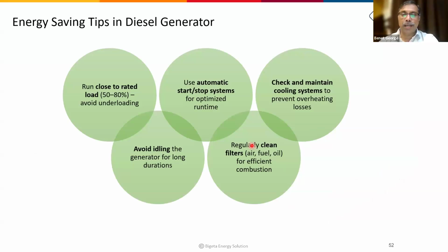Then use automatic start and stop systems. That means whenever the power supply comes back within a short period, you can put the DG off and use the grid power. And check and maintain cooling systems to prevent overheating and losses. Avoid idling the generator for long durations. Regularly clean the filter. If the filter is not cleaned, it will affect the performance of the DG set.